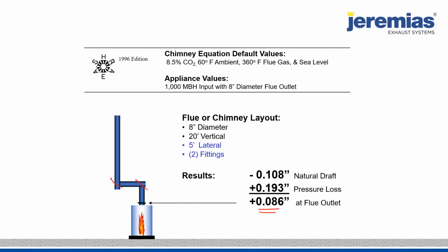This is where we stop and say, okay, something has to change. We need to increase the draft. We could make the stack taller. You know, Jeremias would love to see all the stacks around Boston 50 feet above the roof line. You have to decrease the pressure loss. One option is a mechanical draft fan, but that's the last resort. You always want to look at gravity vent systems. So the way to reduce the pressure loss is to change the stack diameter.